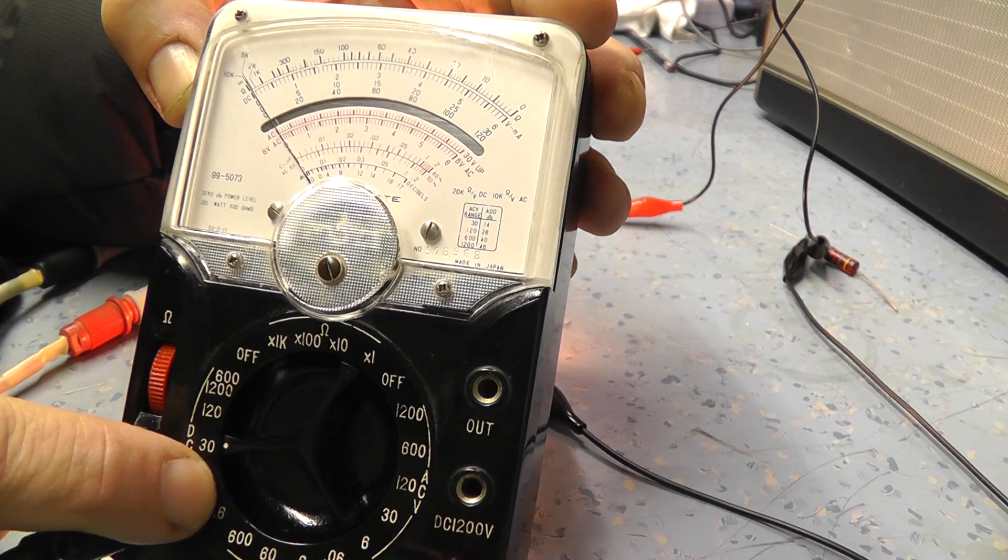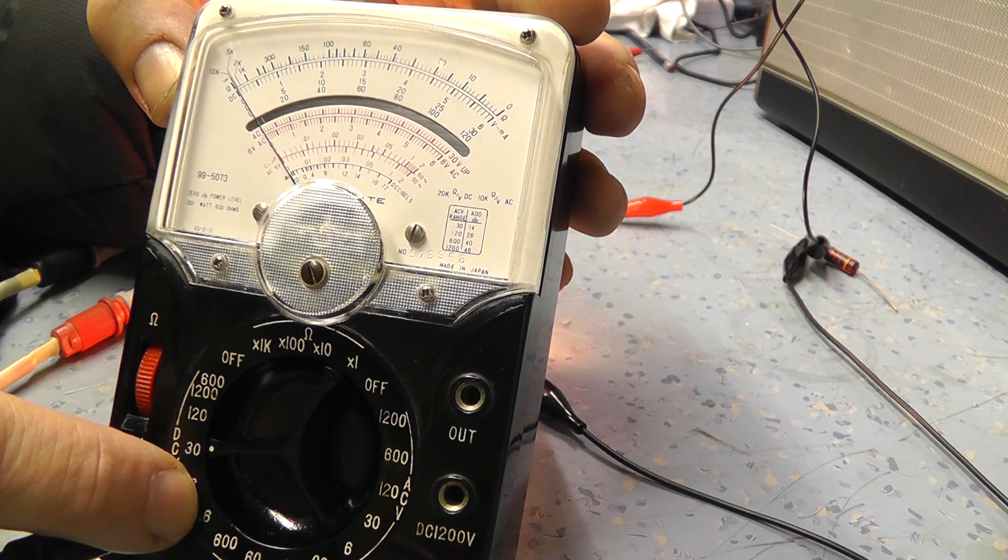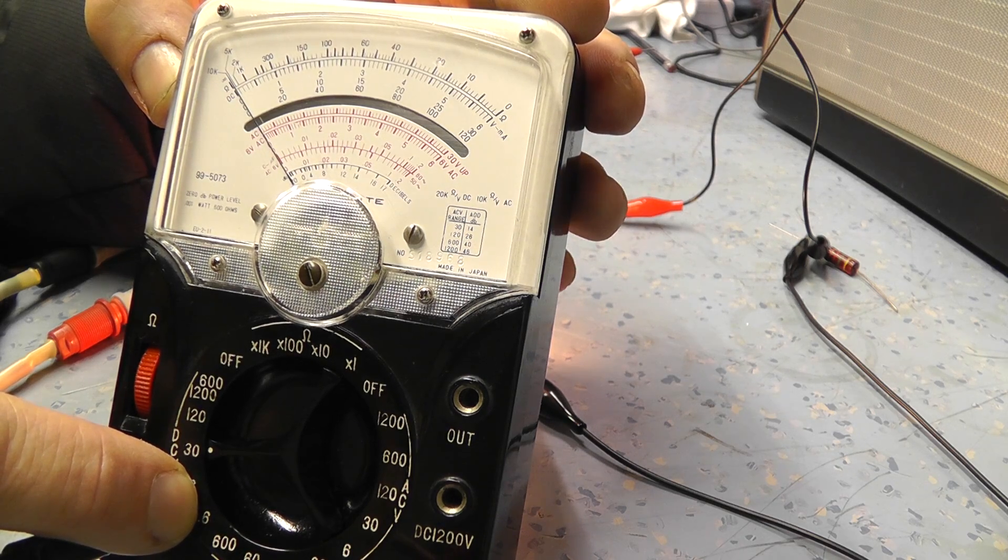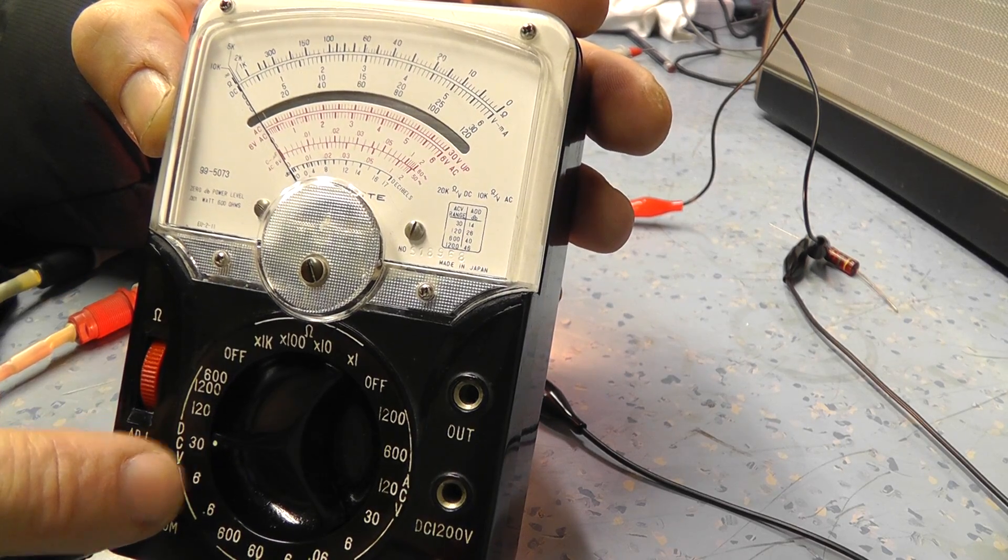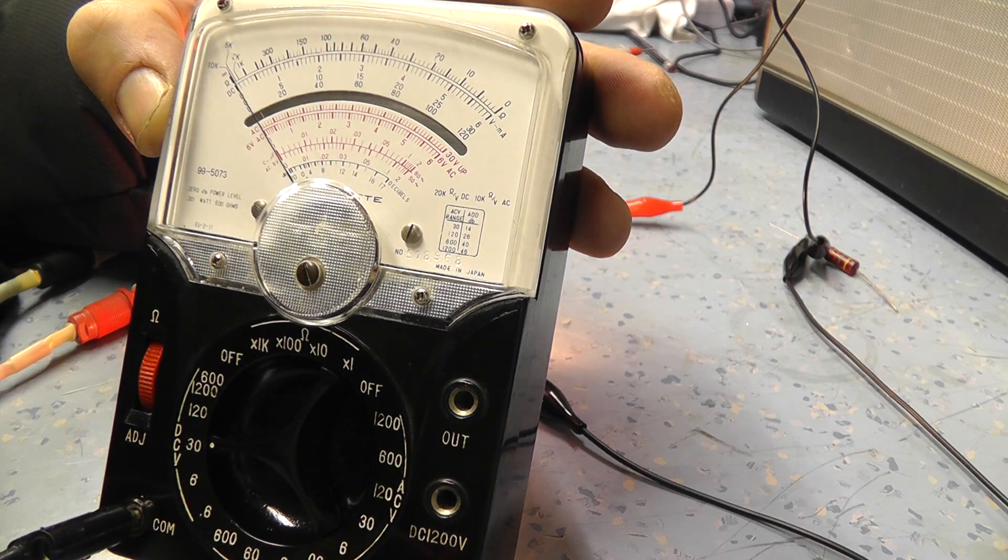This works on AC as well. The same thing if you've got problems with wiring in a barn or something like that, where you can't get the supply through and yet your voltmeter shows it has got 240 volts coming through. Same thing. Use an analogue meter. Put a bit of load on the circuit and it might help you avoid a lot of head scratching and confusion.